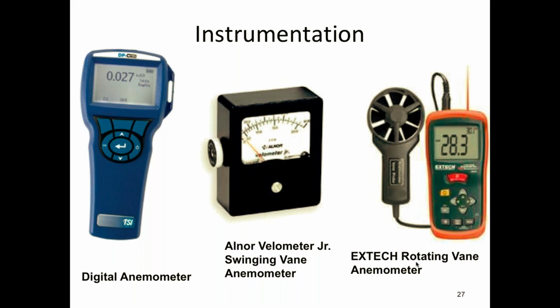Any instrument that measures the velocity of air is called an anemometer. Right? You have digital anemometers, which have a digital readout. You have analog anemometers such as this, and you have different mechanisms for these things to work. This one uses an axial fan blade. I think I got one of these here. Do I have it out there? I know I have it. Let's see. There it is. This is called a vane anemometer.